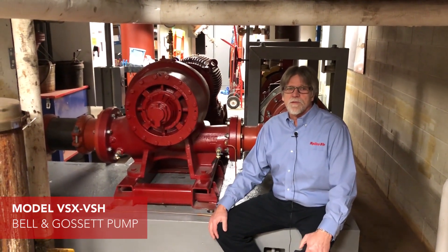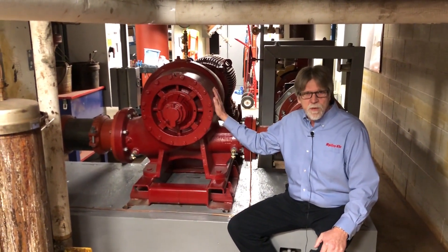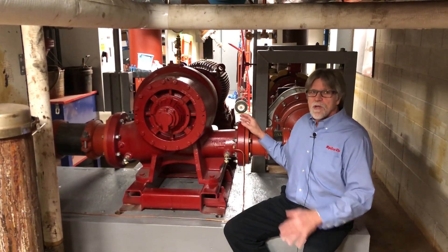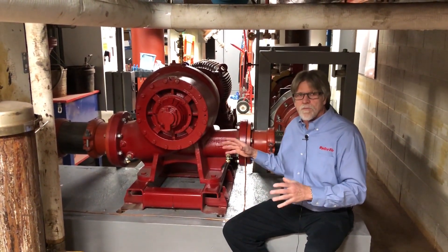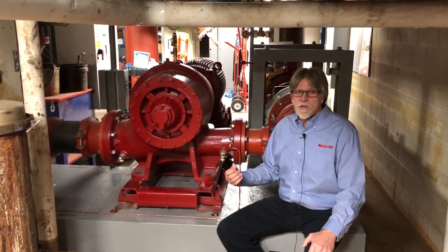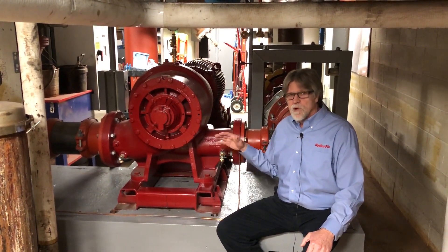We're at the VA Hospital in Milwaukee, Wisconsin on the 10th floor mechanical room where we replaced a horizontal split case pump with the B&G vertical split case pump. It ended up being a smaller suction and discharge, fit better on the pad, and everything was so much smaller compared to the old horizontal split case. If you listen to the first half of the video when the old horizontal split case was in here, the noise level is completely different — it's dropped dramatically.